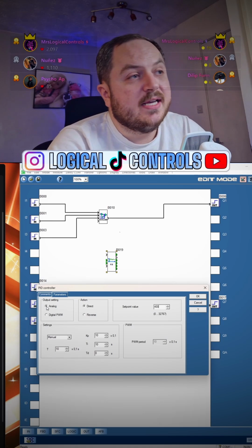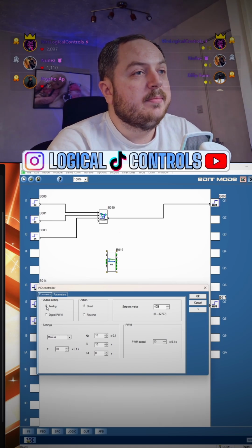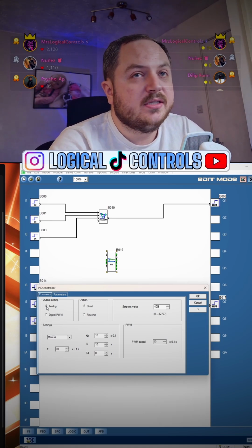These smart relays can have analog outputs, so it can be a 4 to 20 milliamp, or a 0 to 10 volt, though you do need an expansion unit for that. Also, if you've got a transistor one, you can do it through PWM.